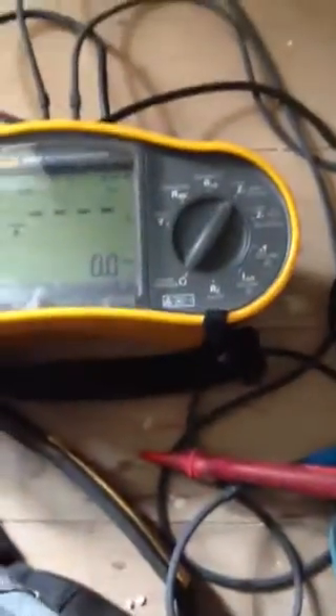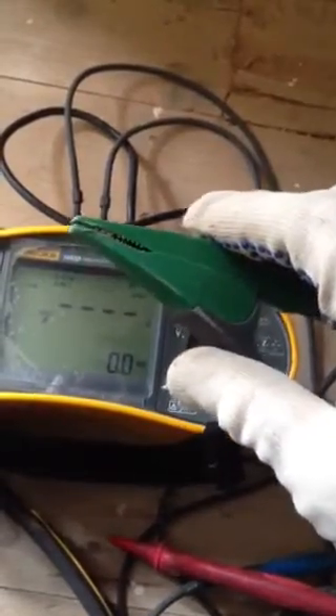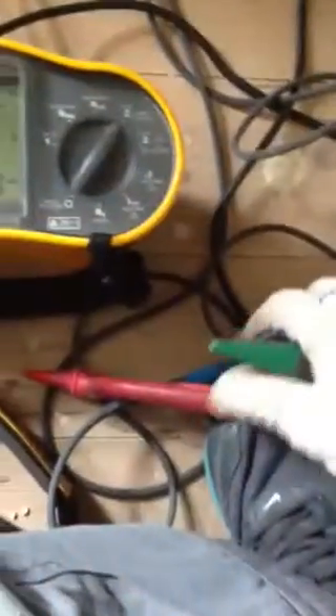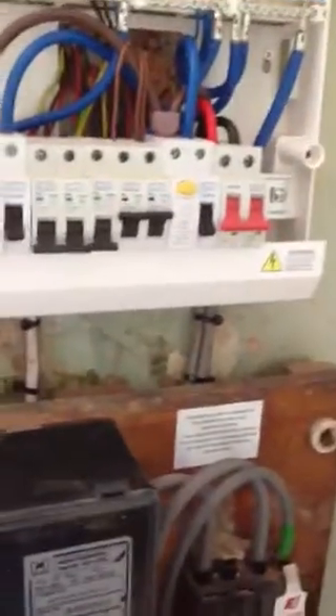I prefer to use the crocodile clip for the earth. It's nice to click on, fasten onto the earthing conductor, and just use the probes for the live and neutral. It's always important to wear extra safety equipment when doing this test. It is a live test, so I tend to wear gloves and goggles.